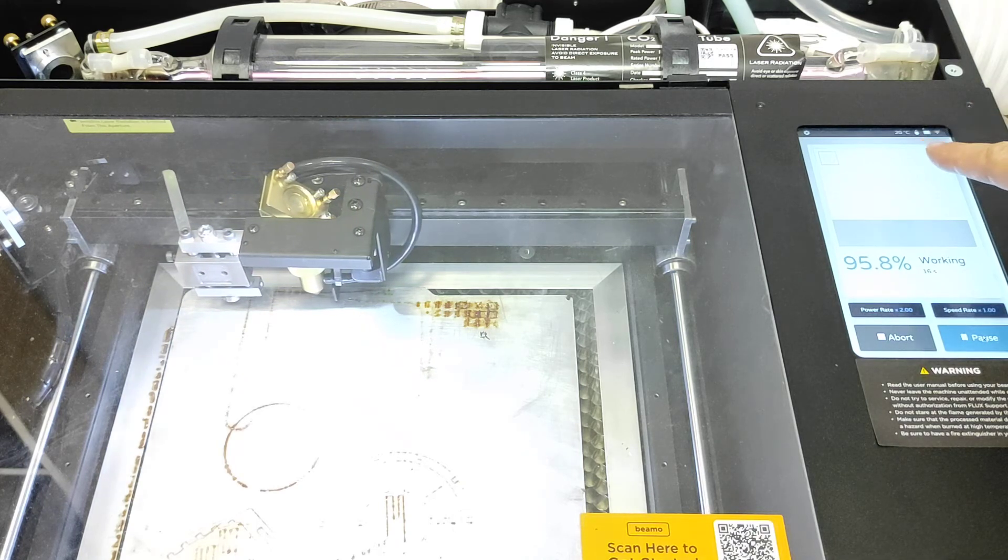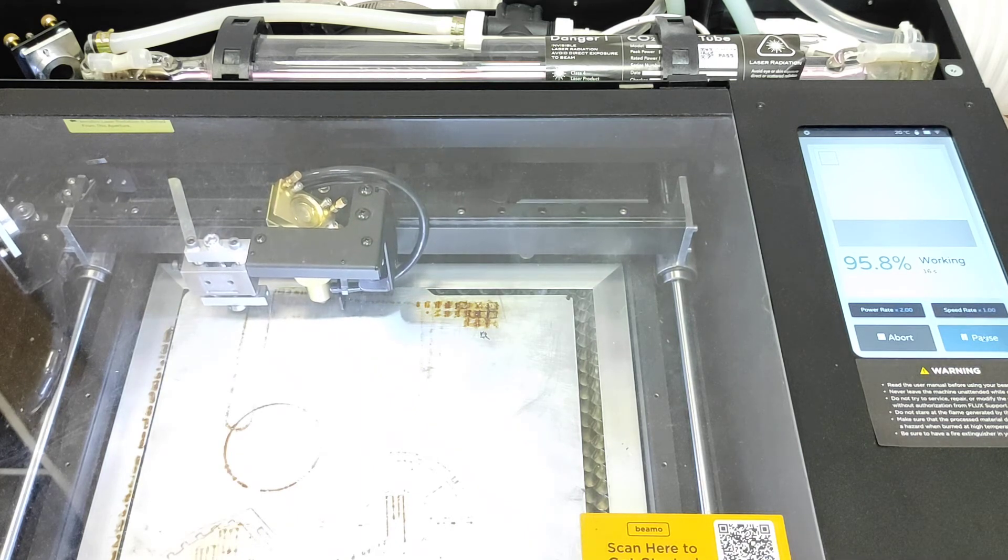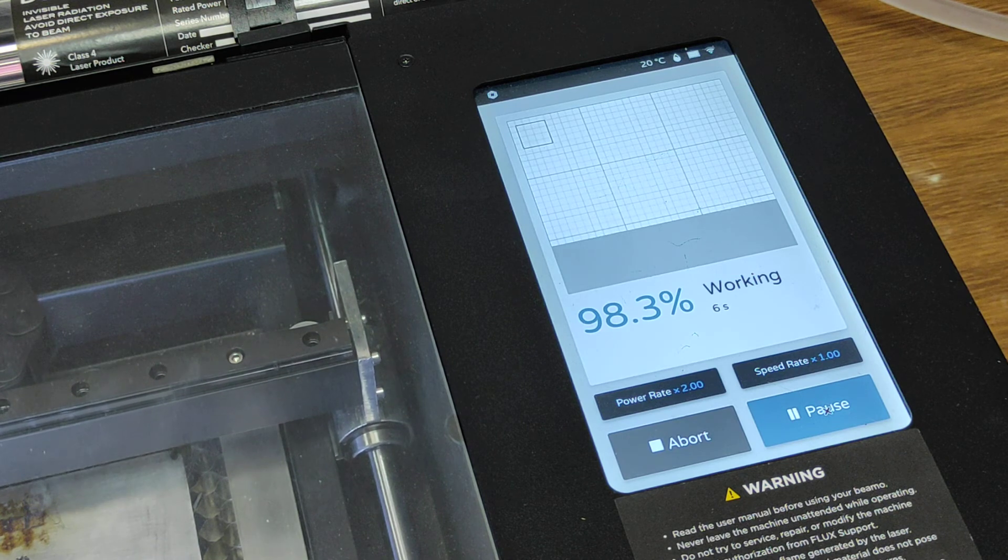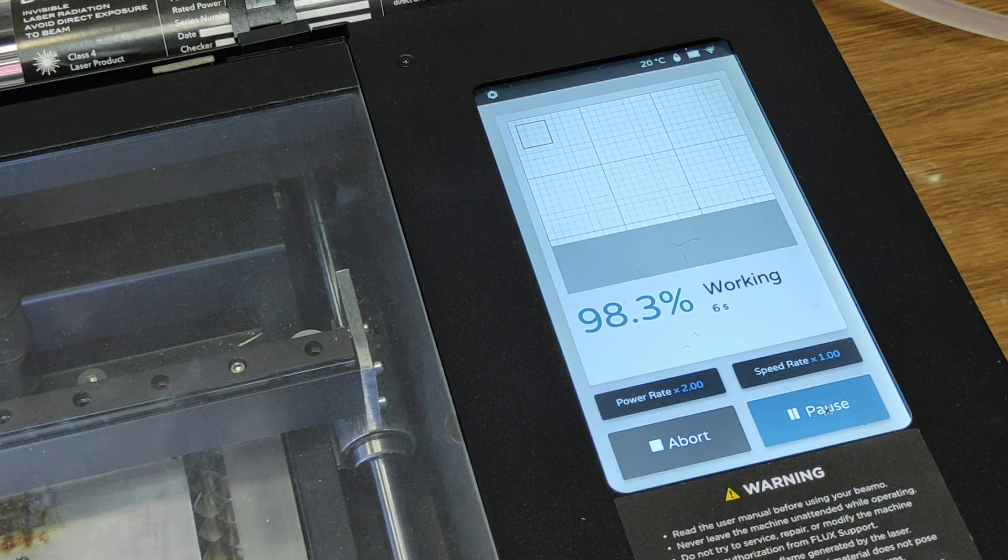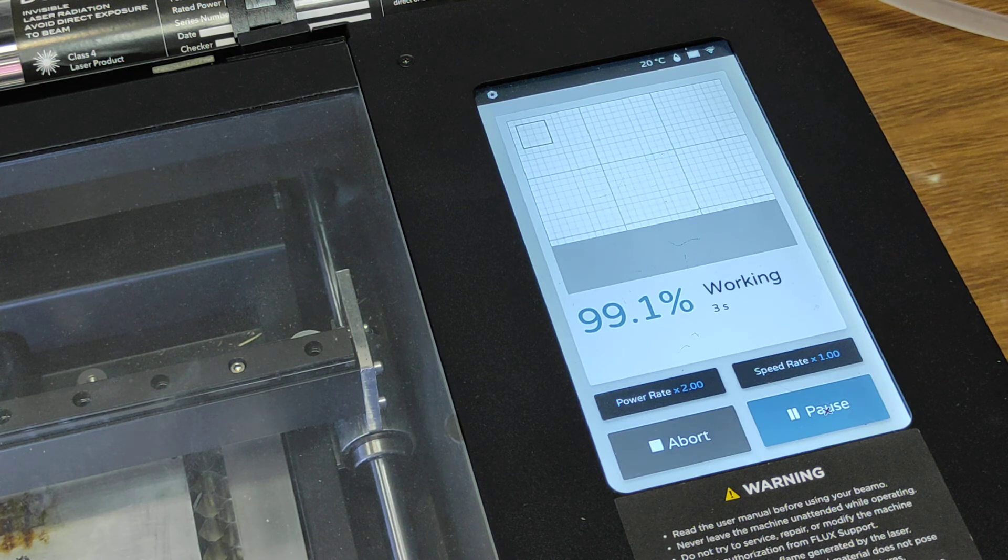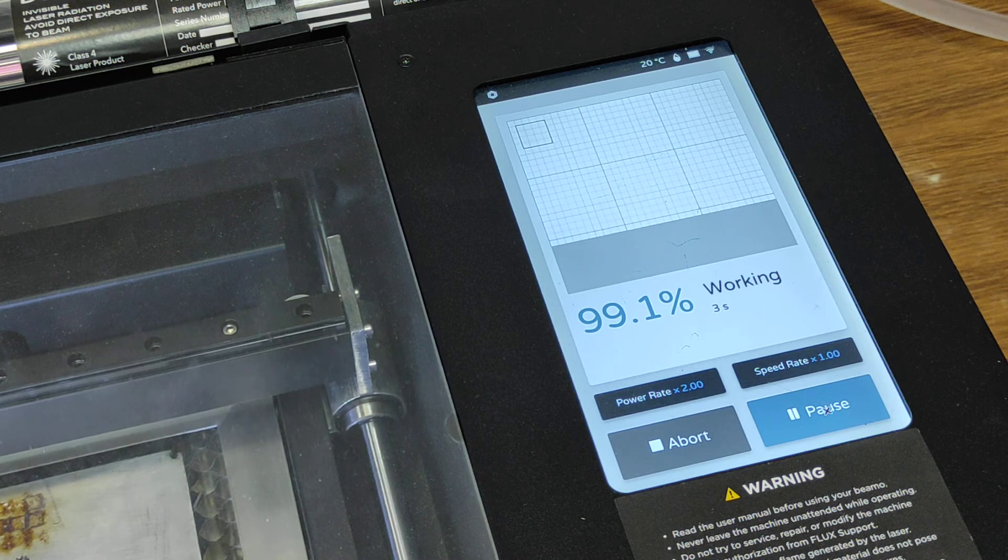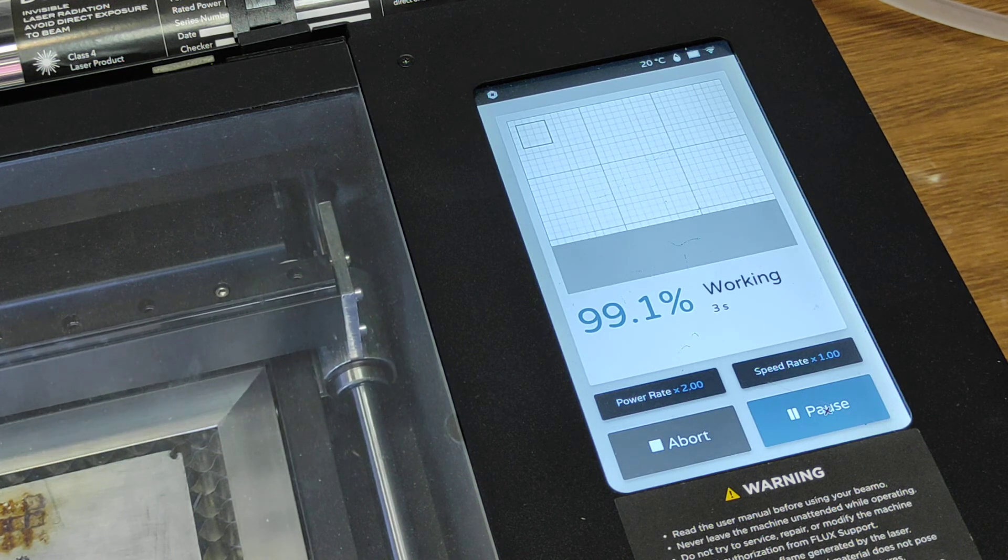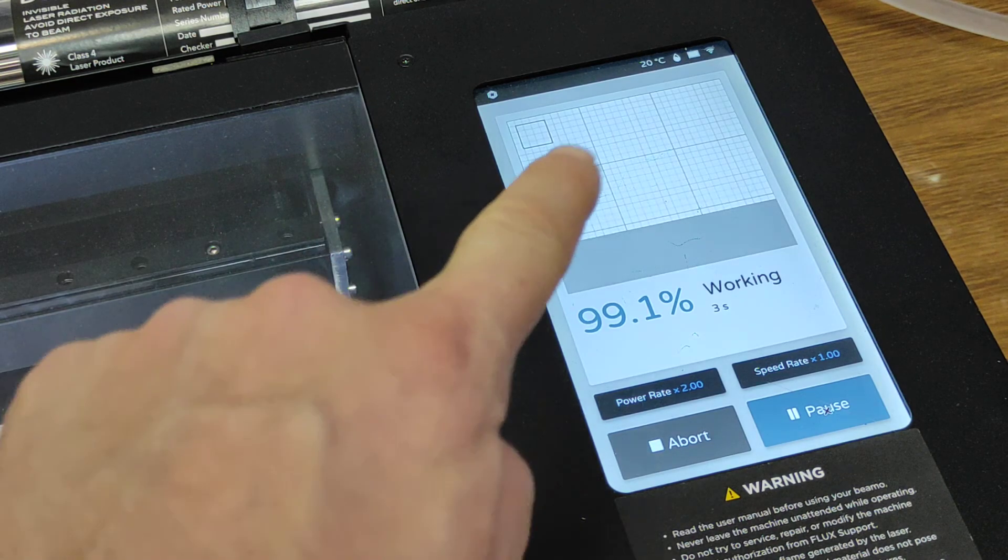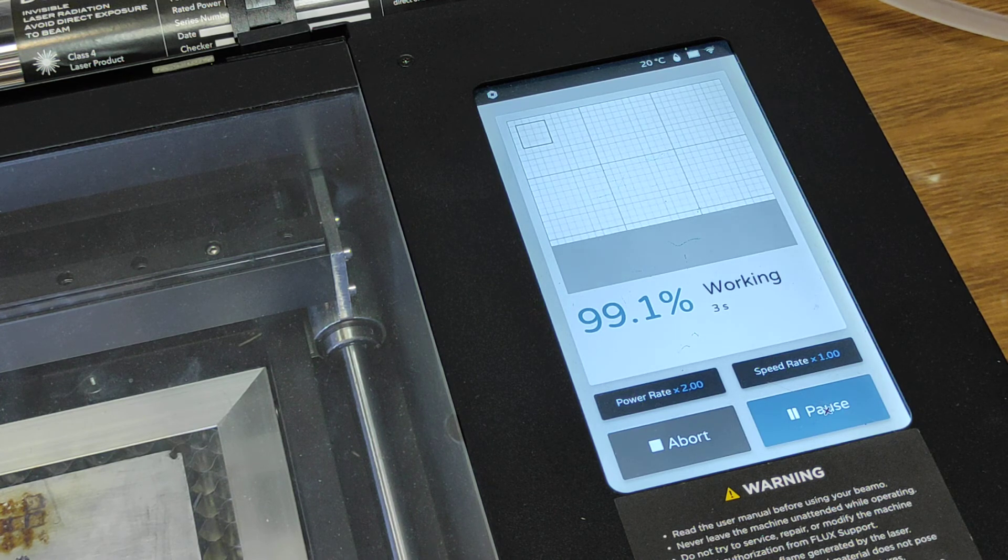The temperature now is 20 and it'll be dropping to 19. So 20 is a stable temperature that allows you to work with the laser and operate it at optimal temperature. The water tank in our chiller has a volume of about a liter, which we can actually increase. You'll see once the laser stops working the temperature will drop significantly.